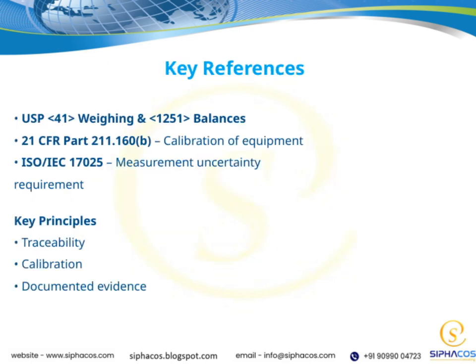Let's take a moment to look at some key references that underpin our quality and compliance efforts. First, USP <41> and <1251> provide essential guidance on weighing and balances, emphasizing the importance of accuracy and reliability in our measurements. Then, there's 21 CFR Part 211.160(b), which focuses on the calibration of equipment, highlighting that regular calibration is vital to ensure our instruments are functioning properly and producing valid results. Additionally, ISO/IEC 17025 sets the standard for measurement uncertainty requirements, reminding us that understanding and minimizing uncertainty is crucial for credible data. Moving on to the key principles that support these standards: traceability, calibration, and documented evidence.